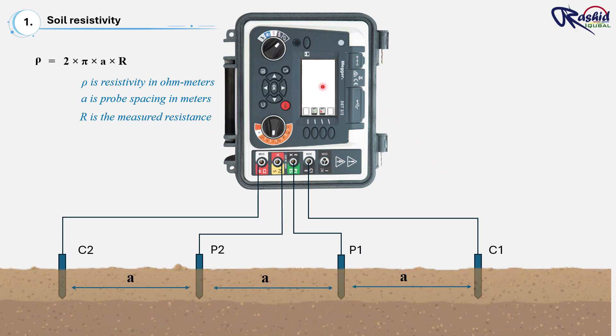Let's take an example. If probe spacing is 3 meters and after measuring from the device we get resistance is 20 ohms, so we can put this value in that formula: ρ = 2 × π × 3 × 20. This is 20, this is the resistance what we measured from this device, and we maintain 3 meter distance. So this is the 3. After solving this equation, we got 377 ohm-meter.